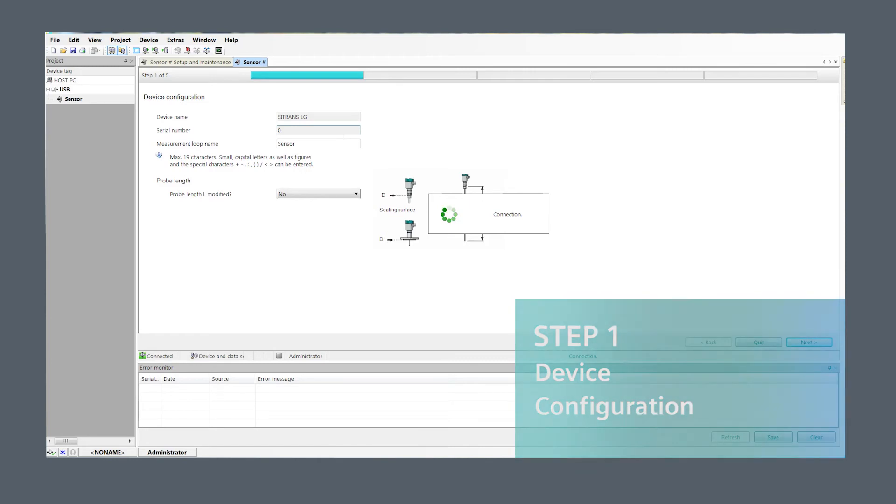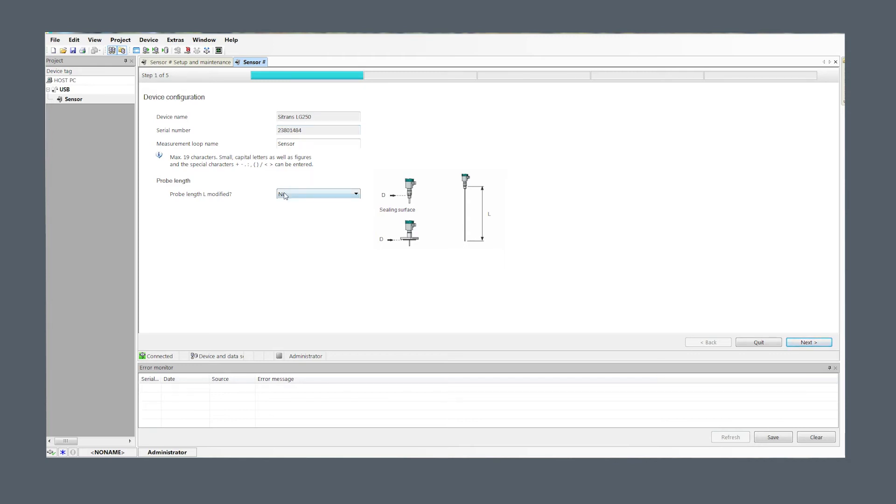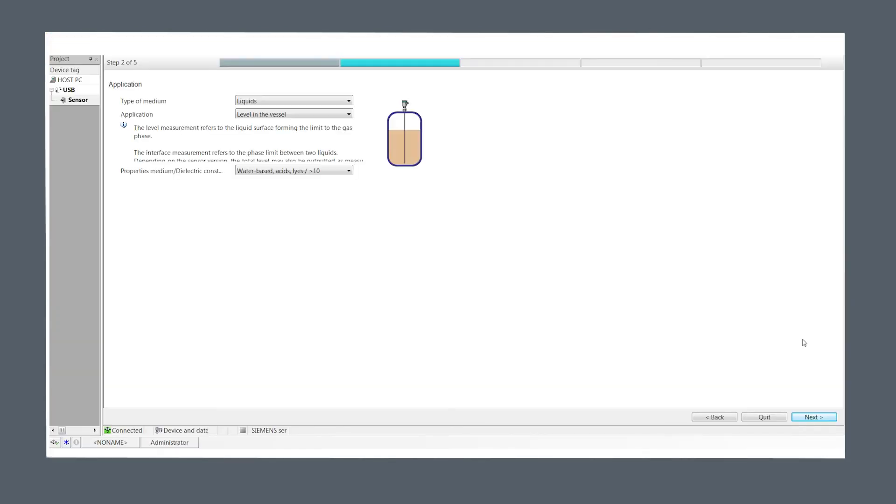Step one, device configuration. You can skip this step if the probe length has not been modified. If the probe has been modified, select yes. If the probe is uncovered, the unit can run an automatic probe length determination routine or you can enter the exact length of the probe.